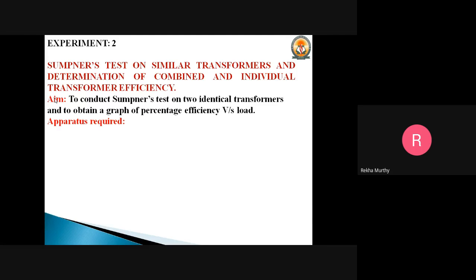Why do we call this the back-to-back test? That is because one transformer is loaded on the other, hence it is called the back-to-back test. The Sumpner's test provides data for determining the regulation, efficiency, and also heating under load conditions. Two identical transformers are used, and whatever power is drawn from the supply is that necessary for supplying the iron and copper losses of both transformers.